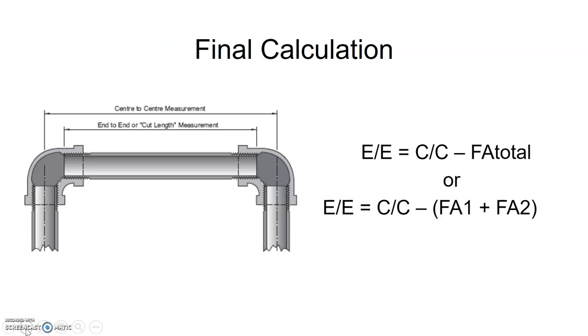So our final calculation will be, in order to find our end-to-end, we need to know the center to center, and then we subtract the FA's. So in this case, we can subtract the FA total, which just means we've added the two FA's together for either side, and now we're going to subtract it from the center to center. Or we could write the formula: end-to-end equals center to center minus, in brackets, FA1 plus FA2, and we're going to subtract that all off of the center to center dimension. And this is how we find end-to-end, knowing our center to center.